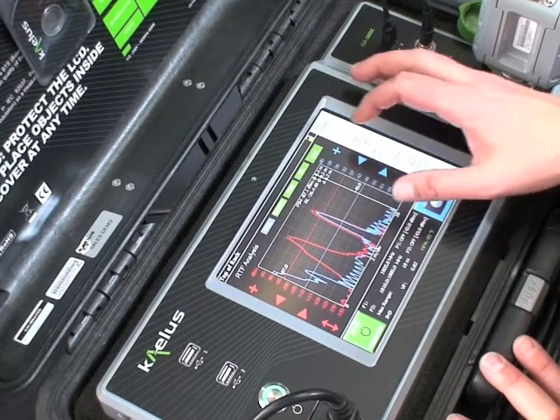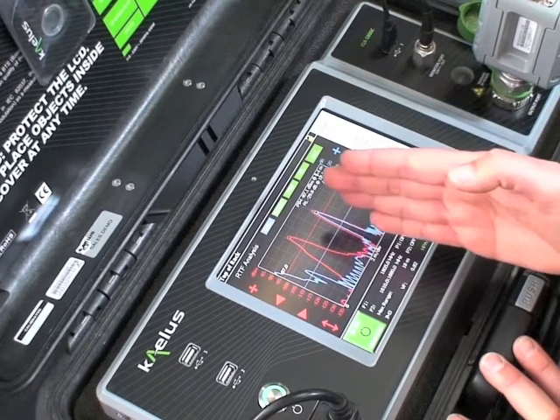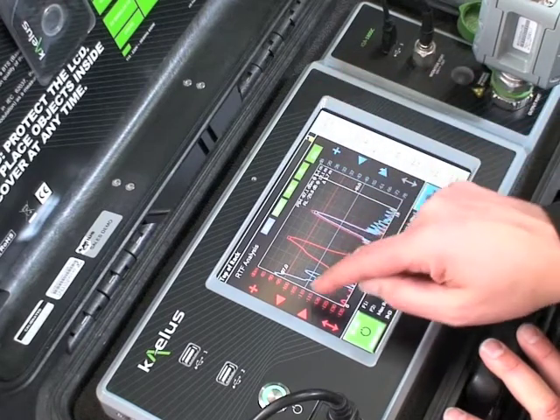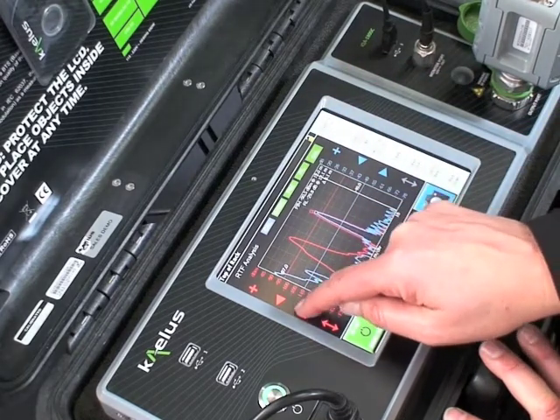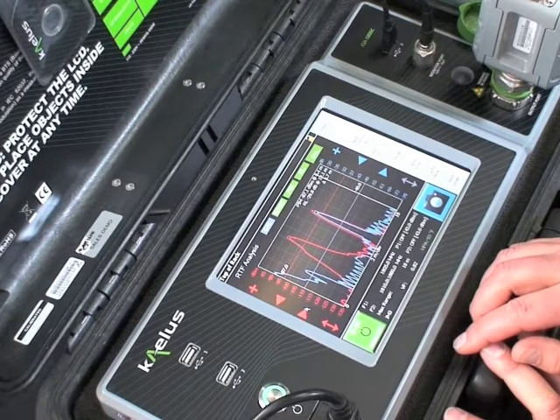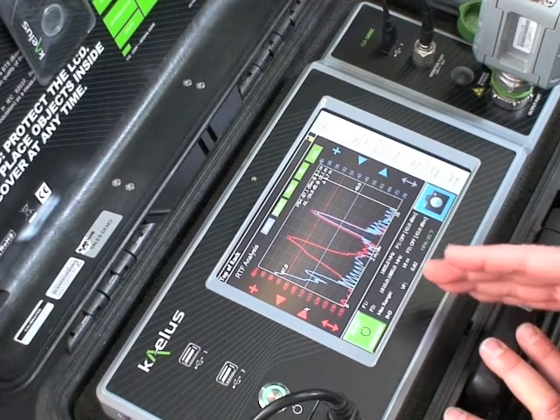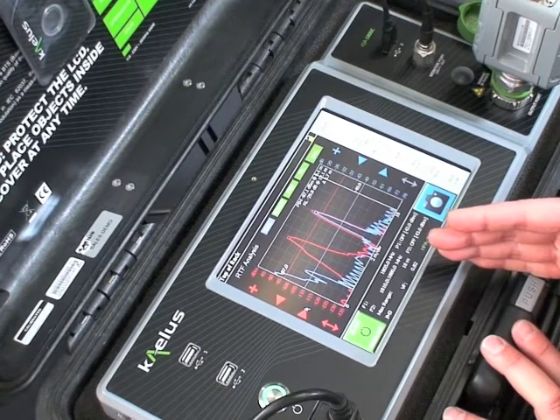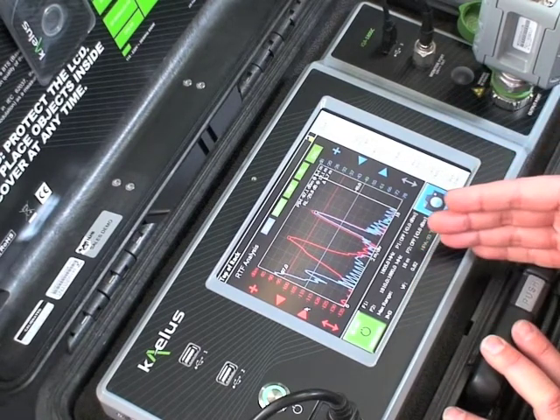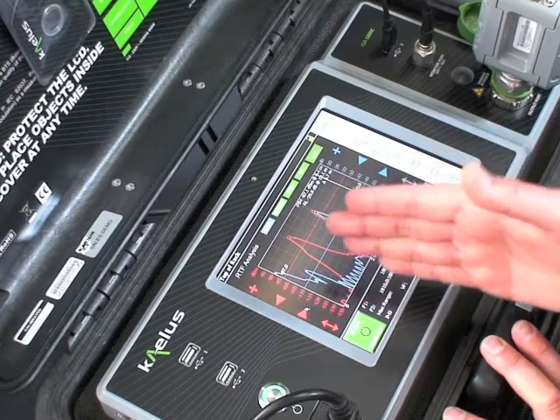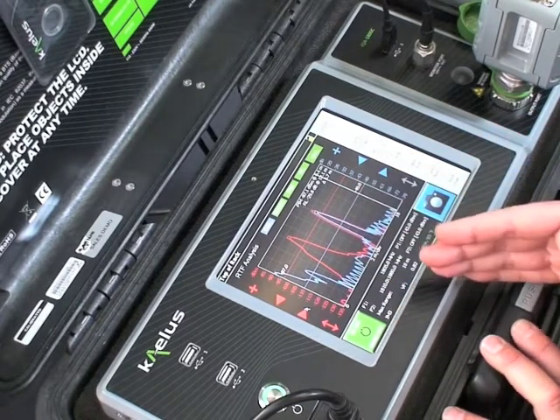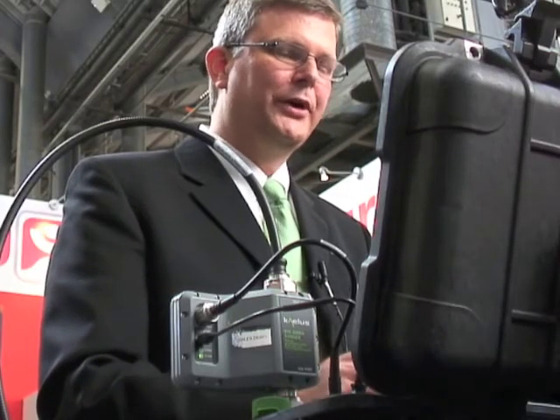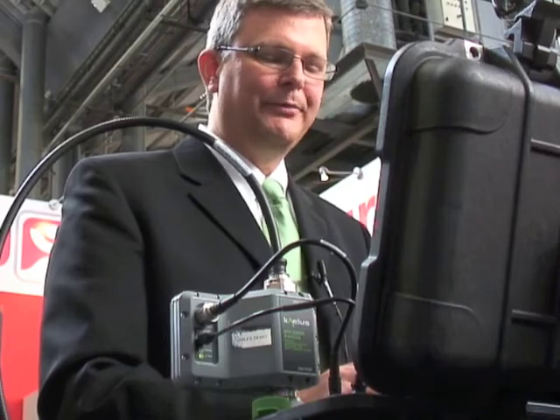The value of this to an operator is it provides the ability to take a known reflection, such as the end of the line, and compare the PIM sources being measured in distance relative to that known location. Instead of having to work from the bottom up to determine the location of faults, we have the ability to work from the top down, measuring how far from a known reflection the PIM fault is. This capability allows operators to much more quickly find and eliminate PIM problems in the field.